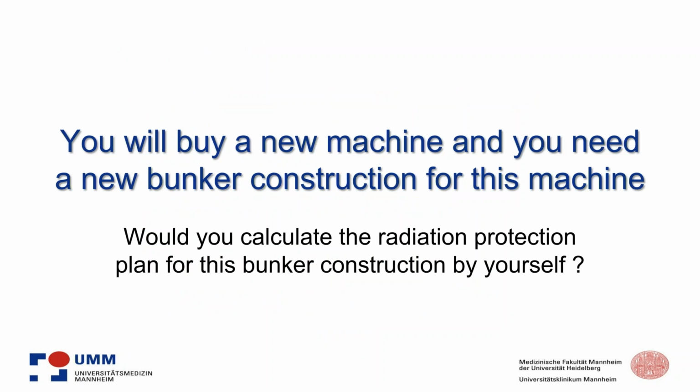So now, this is what you could ask yourself. You will buy a new machine and you need a new bunker construction for this machine. Would you calculate the radiation protection plan for this bunker construction by yourself? You could, but you have to completely understand also the complex examples for this calculation, and the risk that you fail in one or the other point is high.